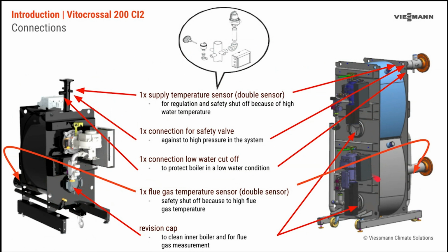However, in the double deckers, as these boilers essentially can operate with some cascade logic, we may have one boiler firing and one boiler not firing. In order to prevent pressurized flue gases entering the unfired vessel, it will operate its burner fan, but combustion will remain off. So in order to prevent combustion testing with dilution of flue gases with a running combustion fan, our protocol in CI2 will be to test combustion in the revision caps.